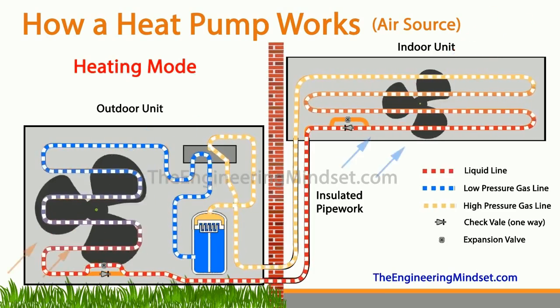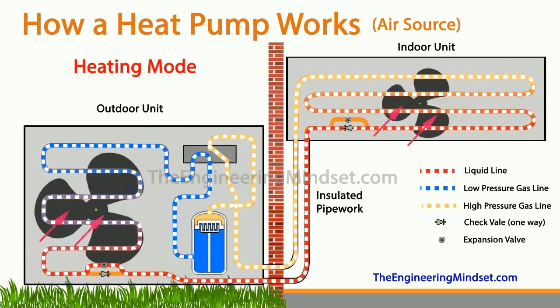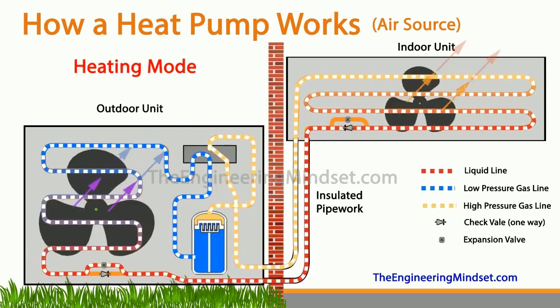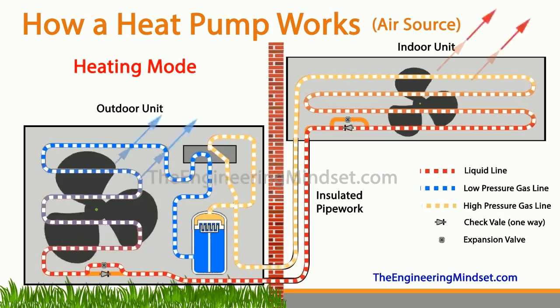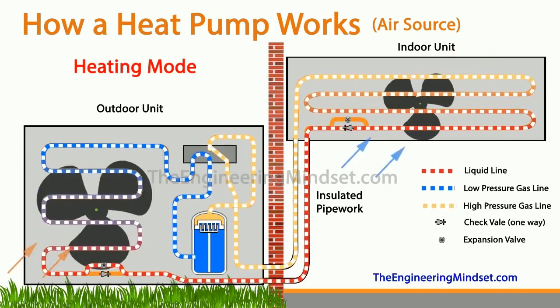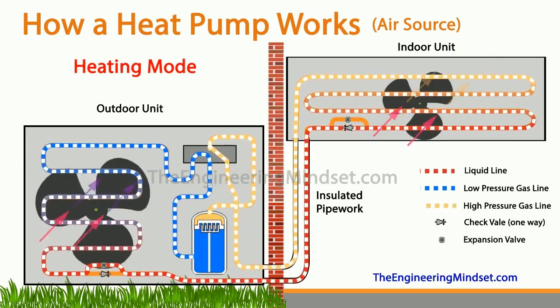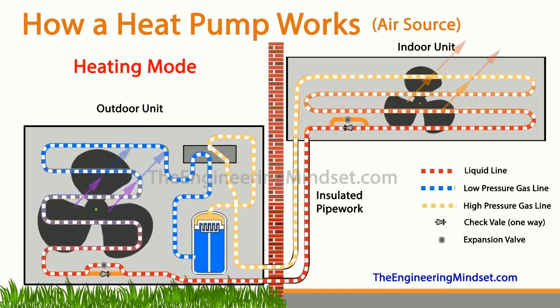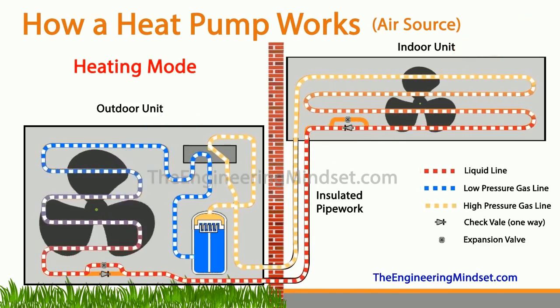The refrigerant enters the condenser, and it enters this as a high pressure, high temperature, superheated vapor, and this will give up some of its energy to the air which is blowing across the heat exchanger by the fan. This condenses the refrigerant and turns it into a liquid.